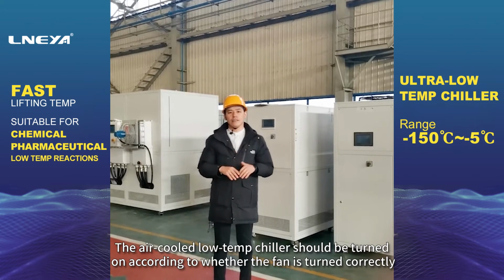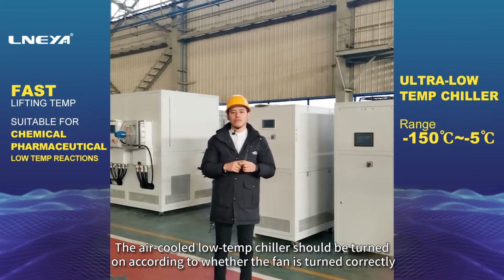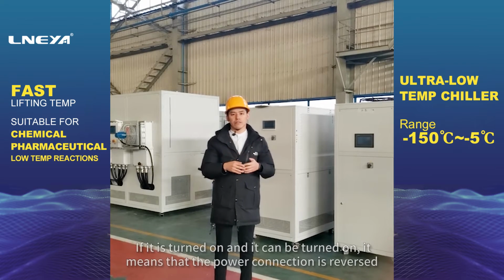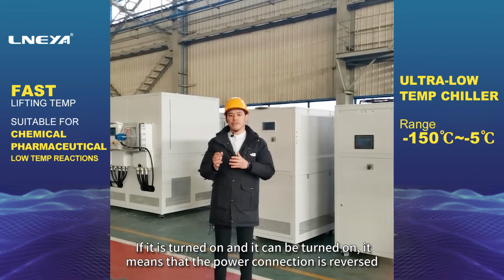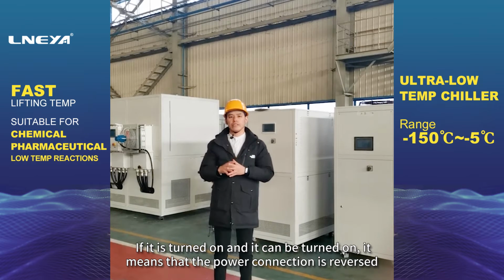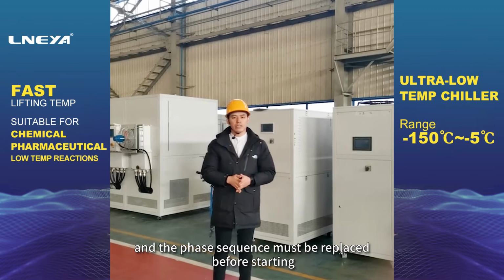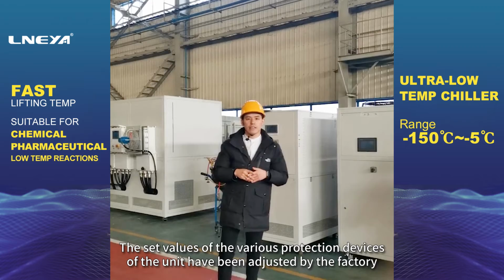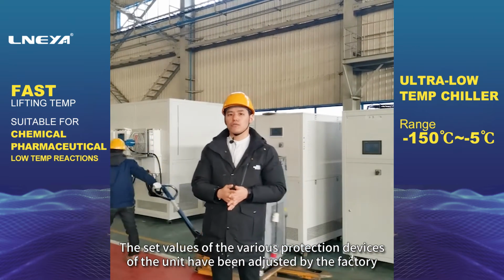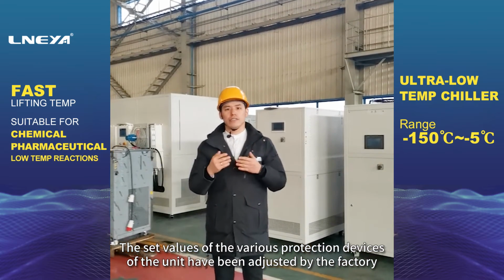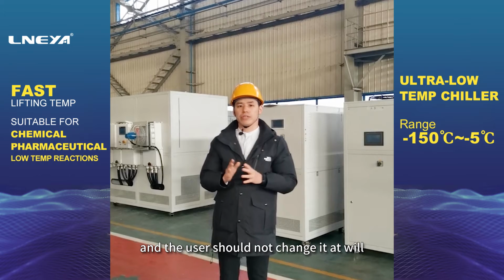First, the air-cooled low-temperature chiller should be turned on according to whether the fan is turned correctly. If it is turned on and it can be turned on, it means that the power connection is reversed, and the phase sequence must be replaced before starting. Second, the set values of the various protection devices of the unit have been adjusted by the factory, and the user should not change it at will.